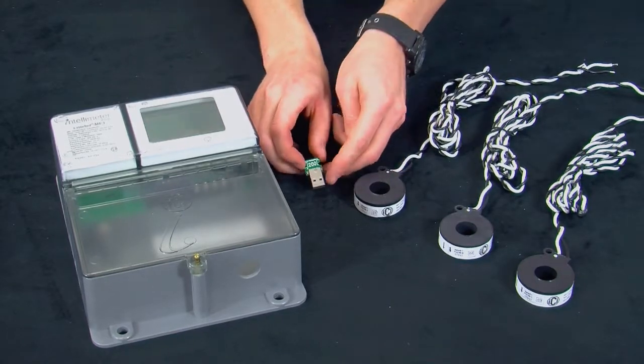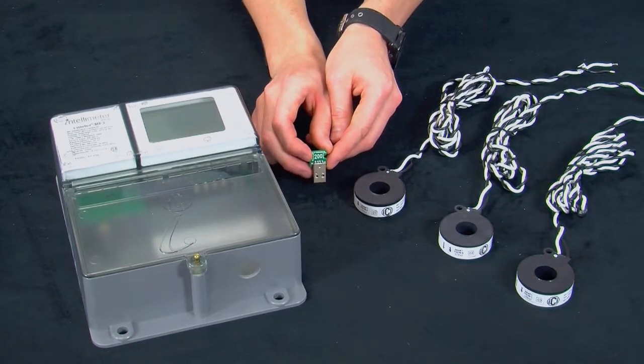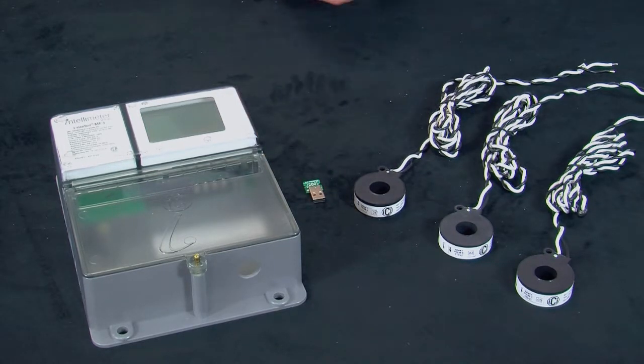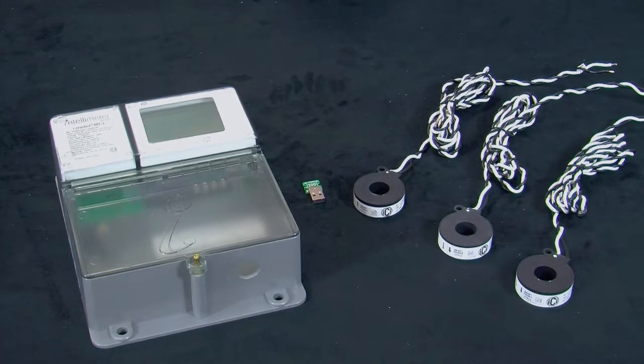And lastly, our CT programming USB dongle. This tells the meter which type of CTs are being used with it. Take a quick moment to go over your paperwork and make sure that the number on the USB dongle matches the rating of the CTs. This information can be found on either your packing slip, shop drawings, or other paperwork provided.